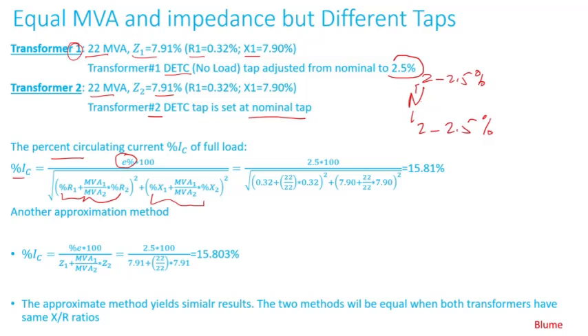Specifically, you take the percent resistance of Transformer 1 plus the MVA of Transformer 1 divided by the MVA of Transformer 2 times the percent resistance of Transformer 2, squared, plus the same ratio applied to reactances, squared. Plugging in the numbers — with a voltage difference of 2.5% — you get 15.81%.